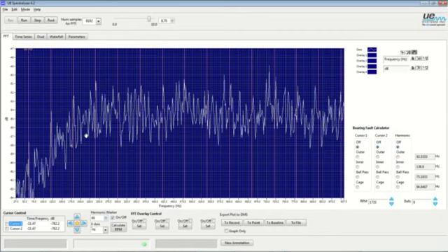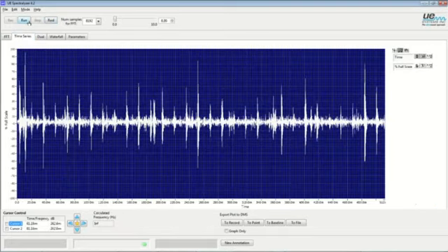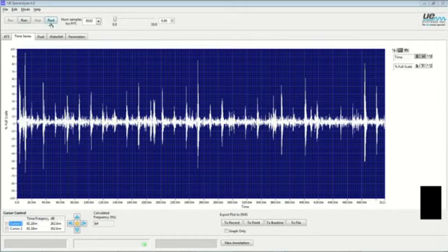Now, in the tonal quality of the recording, you could clearly hear a buzzing sound with, I will call it Rice Krispies, a lot of snap, crackle, pop on top of the buzz. Those are the discharges. Again, using the time analyzer, we can visualize that. And if we watch the entire recording, we're going to be able to see this change, amplitudes and timing. So I'll run this one more time.